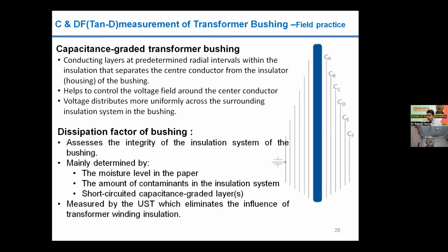Next is the capacitance or the DF measurement on the transformer bushing. Just like the transformer winding health or insulation health assessment, we also do the tan delta testing of the bushing. And generally we talk about the C1 and C2 test. You know that the bushing principal diagram is shown.